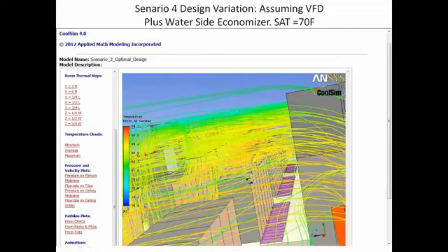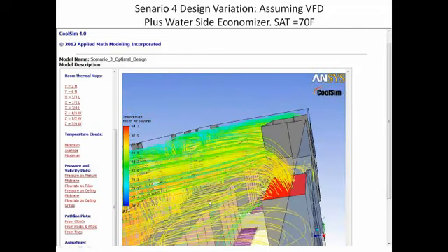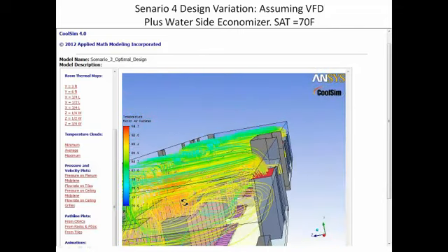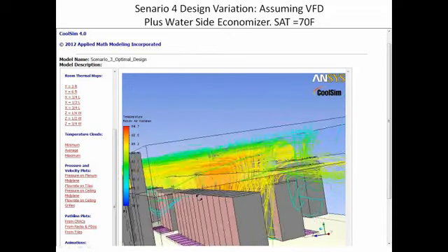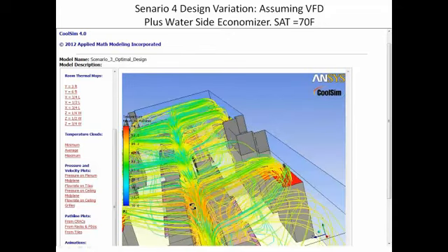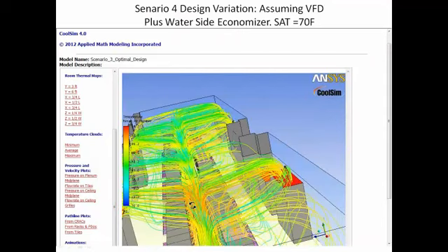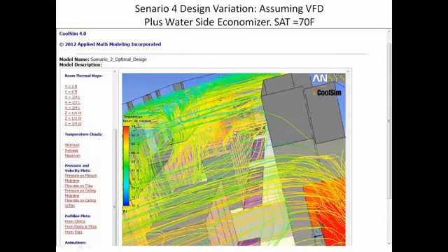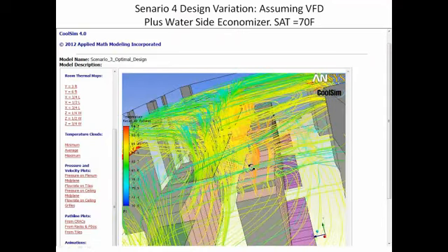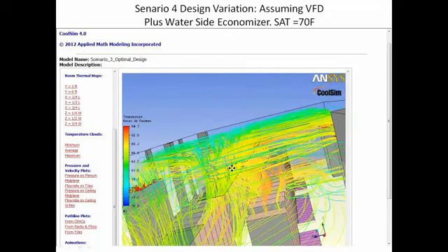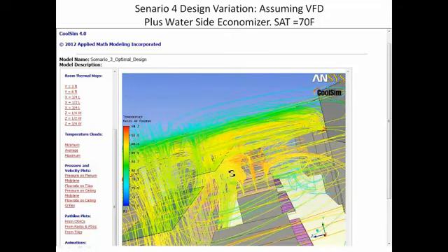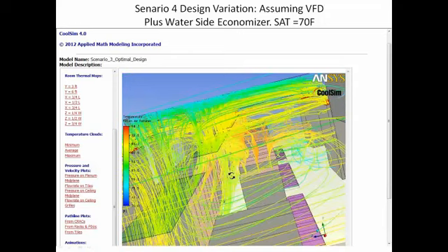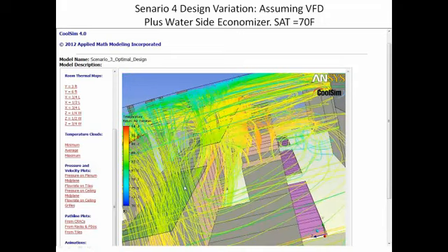For most data center managers, what they do is they understand where the hot spots are going to be, and they just avoid putting high density equipment in those locations. And of course, in a design like this, it's always near the top. Now, you could do some containment, as we talked about. We did not contain in this place. In this case, we did not put curtains in place or anything, but there could be the opportunity to do that.